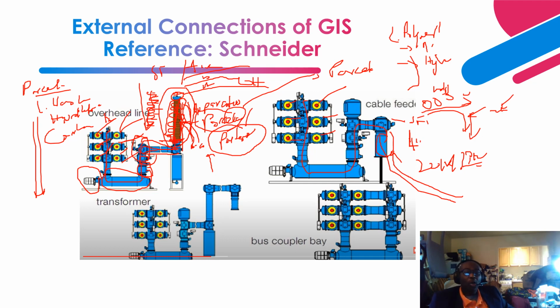Okay. So similarly, this is a double bus arrangement, right? Phase A, phase B, phase C, right? Okay. So as you can see, this is the VT, the voltage transformer that is utilized for metering and protective relays. Then CTs are over here, and this is the breaker operating mechanism. Another external connection to a GIS, right, is an integration to an oil transformer. So if you have a transformer that is here, right? Okay, so like I said, this is a single phase arrangement, right?